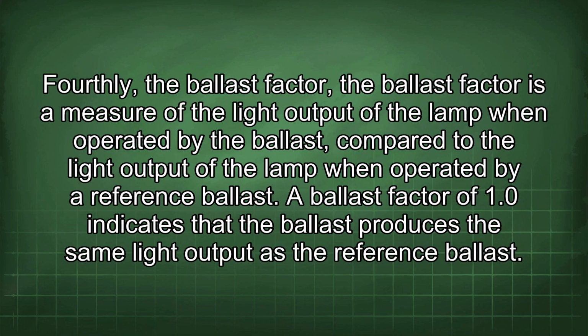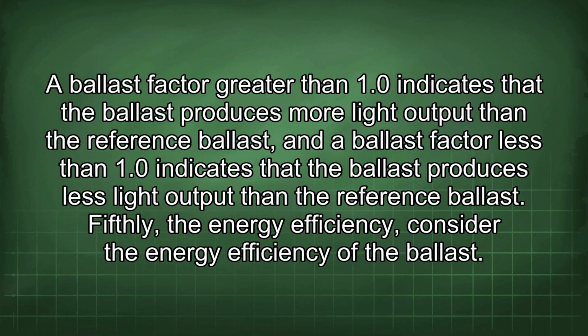Fourthly, the ballast factor. The ballast factor is a measure of the light output of the lamp when operated by the ballast, compared to the light output of the lamp when operated by a reference ballast. A ballast factor of 1.0 indicates that the ballast produces the same light output as the reference ballast. A ballast factor greater than 1.0 indicates that the ballast produces more light output than the reference ballast, and a ballast factor less than 1.0 indicates that the ballast produces less light output than the reference ballast.